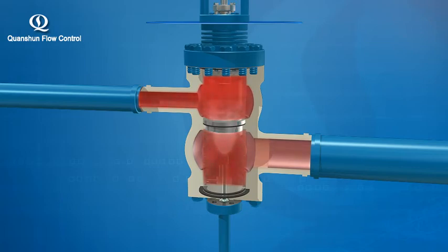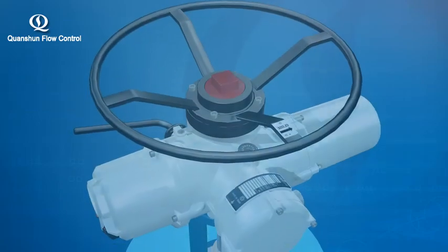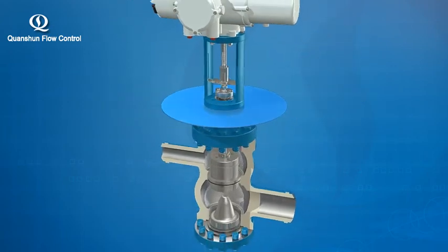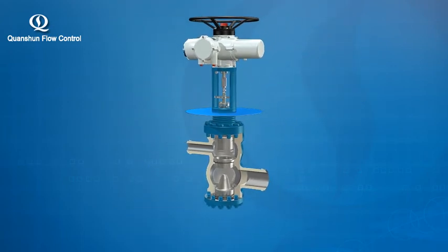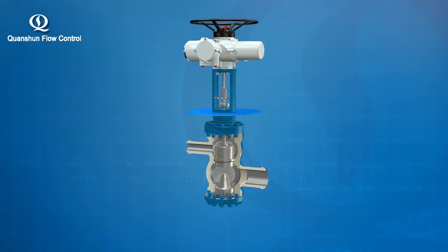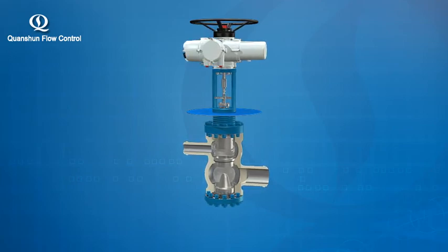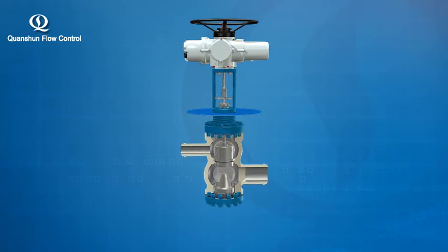The water supply regulator is of multi-stage sleeve type and can be used for high differential pressure regulation after proper selection. The disc and stem are made into one piece, in which the stem is connecting to the linear actuator directly. When the steam temperature inside the steam pipeline changes, the thermoelectric potential of the thermocouple is changed accordingly, and then sent to the electric actuator by way of the temperature transmitter and the regulator. The actuator operates the stem to move the disc, so that the cross-section area of the flow passage changes to control the flow rate of the temperature reduction water, keeping the steam temperature inside the pipeline within the specified range.